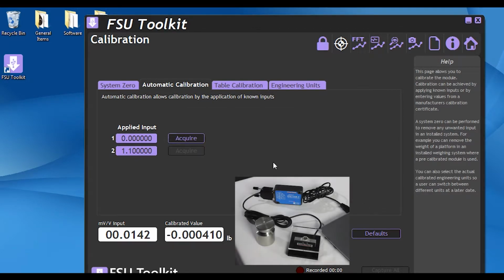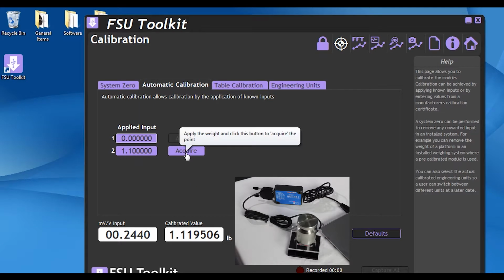Make sure the load cell is unloaded, and then click Acquire. Once it has acquired the 0 reading, now it's ready for you to place the weight on the load cell and then acquire that reading from it. So I placed it on there now. I'm going to click the Acquire button. So now it's taken the reading of the actual weight that's on top of the load cell.